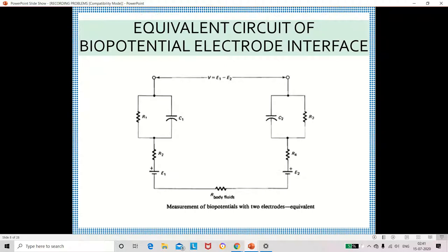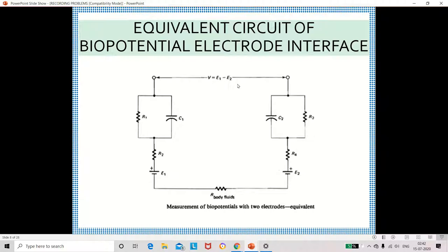This is the equivalent circuit of the biopotential electrode interface. Here we have two electrodes — the equivalent circuit of the first electrode and the equivalent circuit of the second electrode. We connect a resistor because the electrode is kept in body fluid, and the body fluid has some resistivity. We measure the E1 potential across the first electrode and the E2 potential across the second electrode, and find the difference: V = E1 − E2.